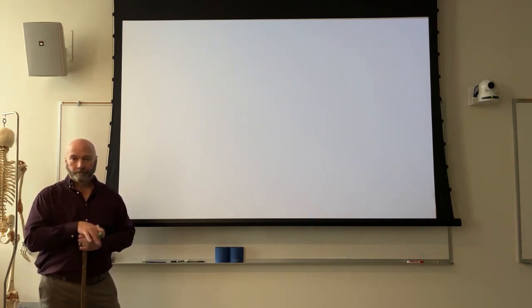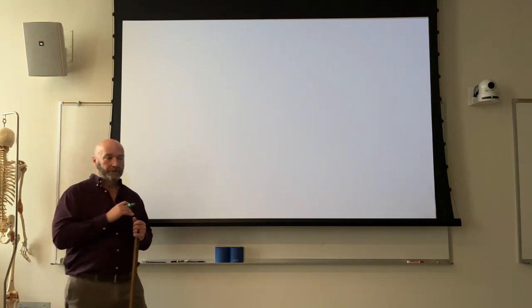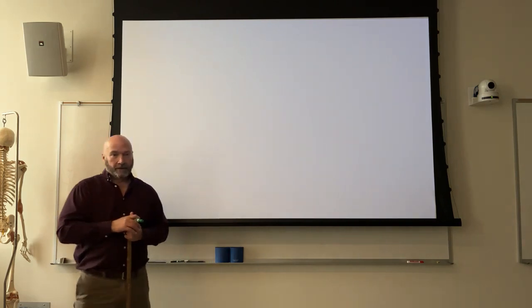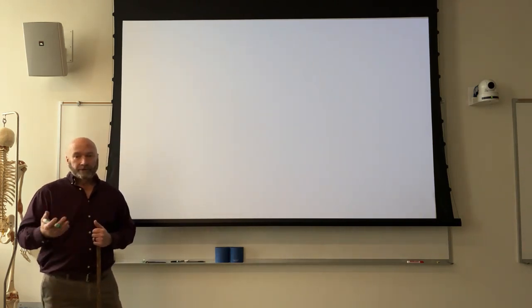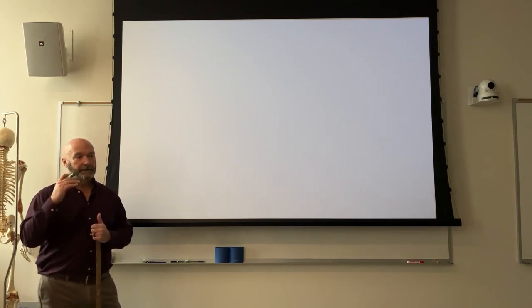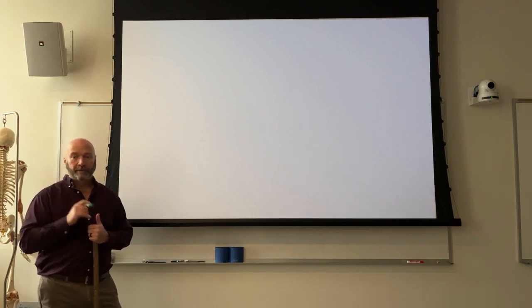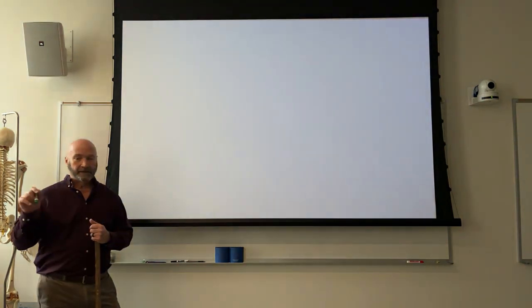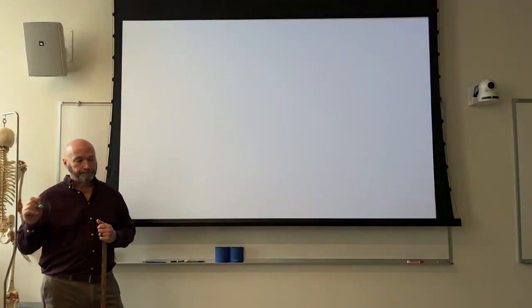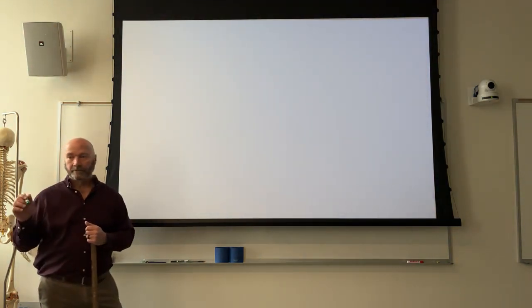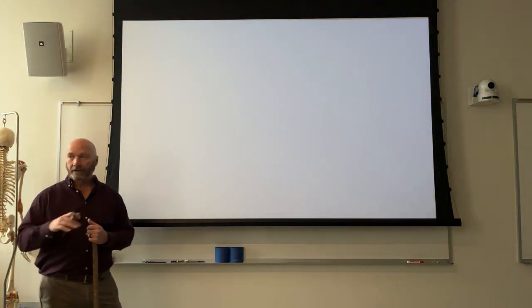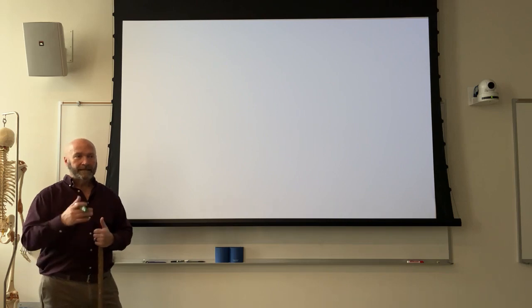IR exposure doesn't change with focal spot size change. It should not, because your tube output shouldn't change. Then your IR exposure shouldn't change, patient exposure shouldn't change. As long as your machine is calibrated properly, there should be no difference between large and small focal spot, with the one exception that some or all of your machines are not going to let you make an exposure with high mA on a small focal spot. But that's exposure limited. That means you're not going to be able to make an exposure.